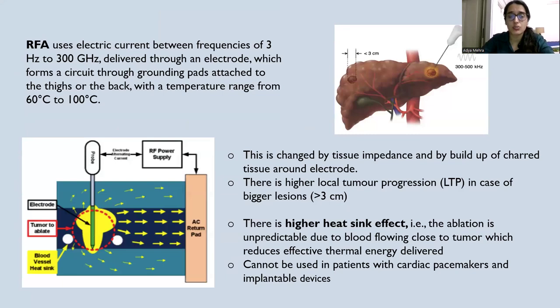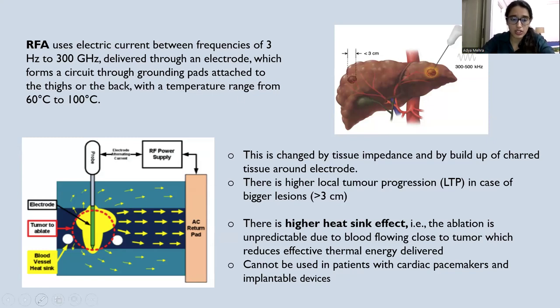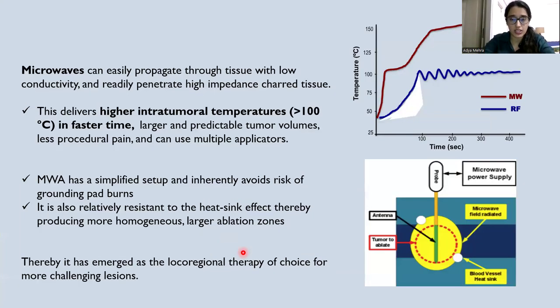RFA uses electric current between frequencies of 3 Hz to 300 GHz delivered through an electrode which forms a circuit through grounding pads attached to the thighs or back of the patient, with a temperature range from 60 to 100 degrees Celsius. However, this is affected by tissue impedance and build-up of charred tissue around the electrode. There is higher local tumor progression with bigger lesions and a higher heat sink effect — ablation is unpredictable due to blood flowing close to the tumor, which reduces effective thermal energy delivered — and it cannot be used in patients with cardiac devices.